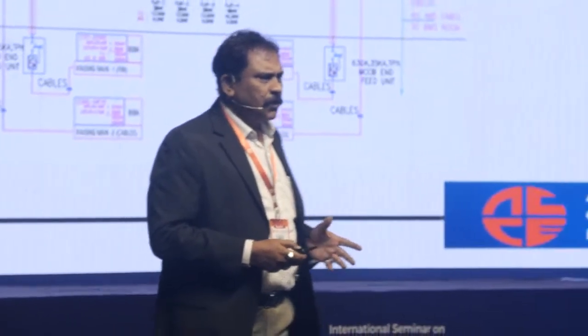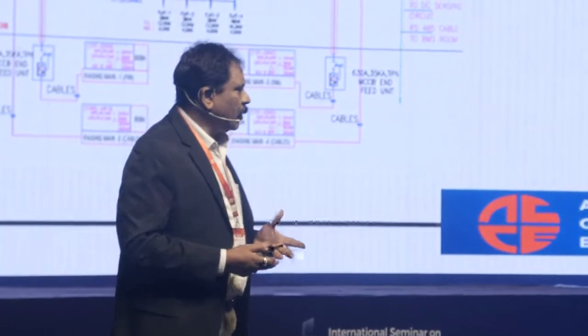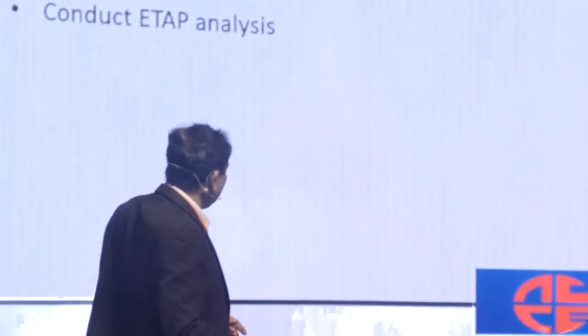Any building up to 200 meters can generally go with LT distribution, but anything beyond that may require bus risers along with redundancy and HT distribution. The bus ducts are highly reliable, with low-cost installation and high current carrying capacity. They can also have fire barriers so fire will not spread from one floor to another, plus high fault handling capacity and fewer terminations compared to cables.